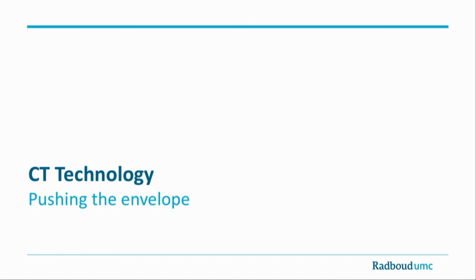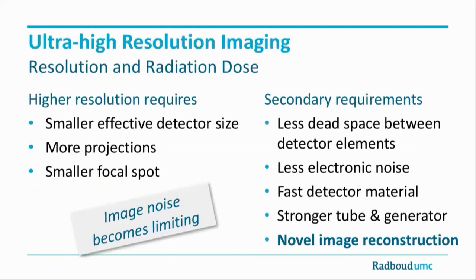Now let me go to something completely different: CT technology, and how it is pushed forward by artificial intelligence, especially for higher spatial resolution. To achieve that, you need smaller detector sizes, more projections, and a smaller focal spot. All of these create image noise, which becomes limiting. So you reduce noise by reducing dead space between detector elements, reducing electronic noise, getting better detector materials, and a stronger tube. But most importantly, you need novel image reconstruction techniques.